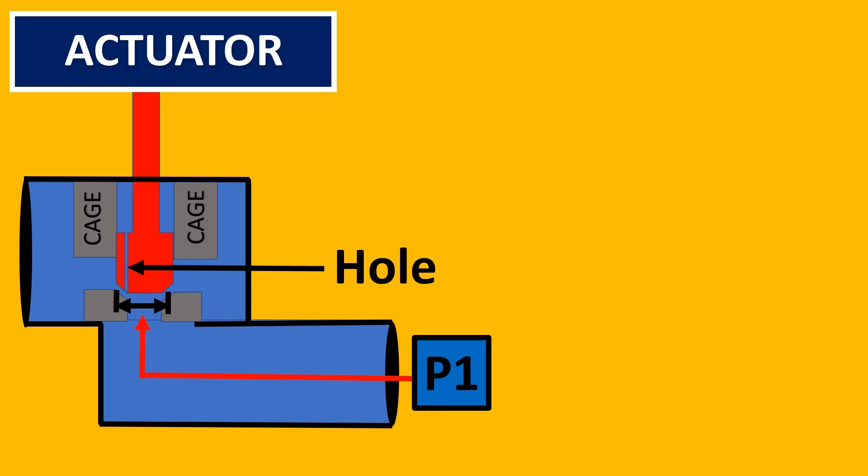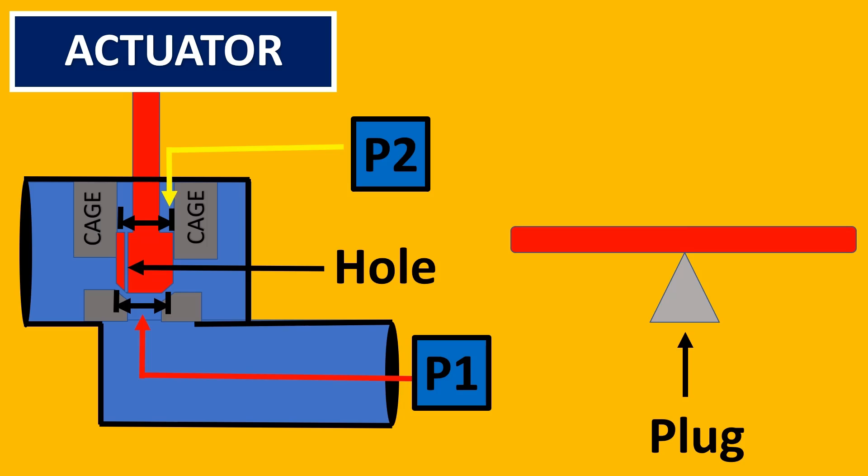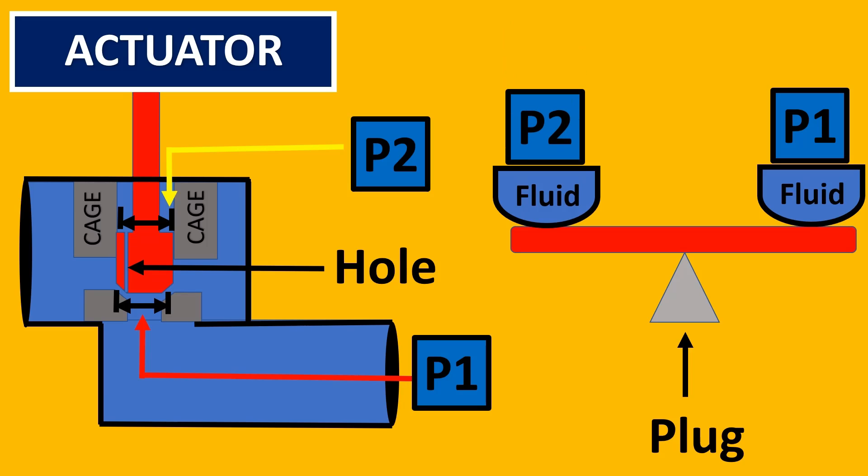Here, let's imagine this is the force P1 acting and here this force P2 acting. If you take the same example of a seesaw, on one side is the fluid force P1, but on the other side approximately the same force P2 is acting on the trim. Now the actuator has to put very little force to move the plug assembly.